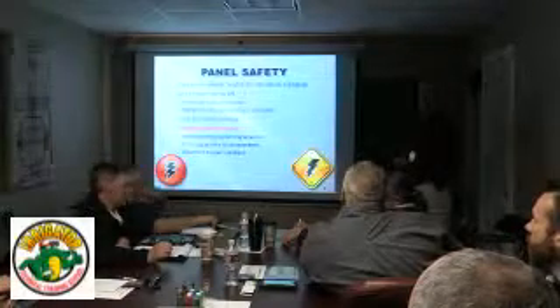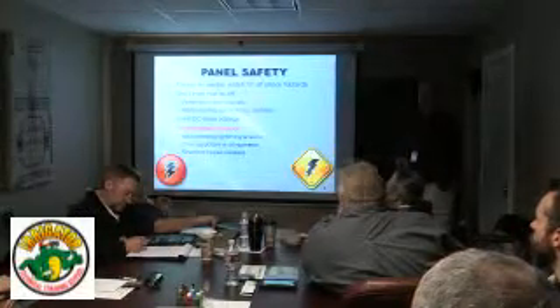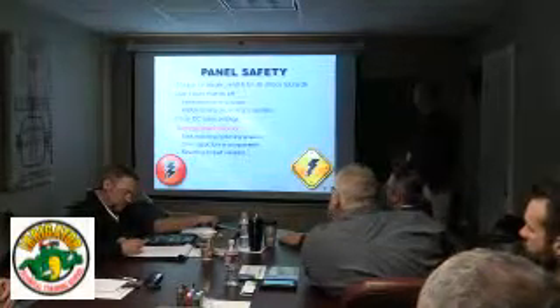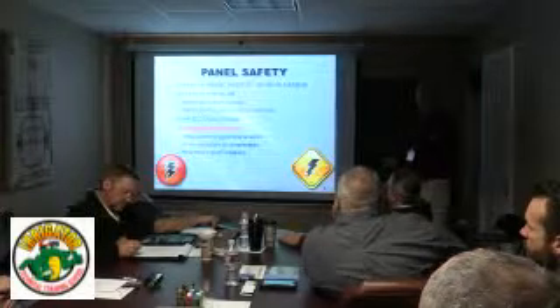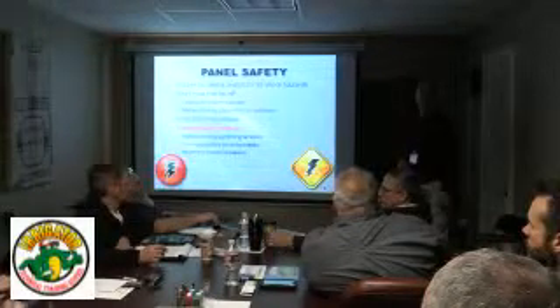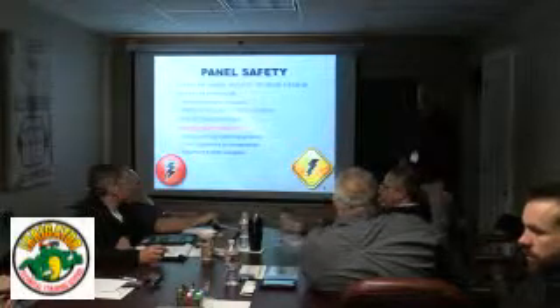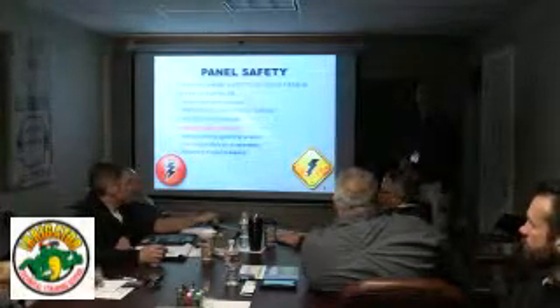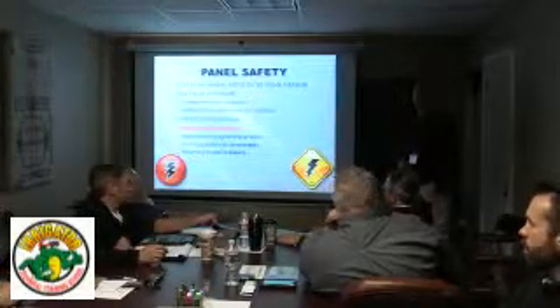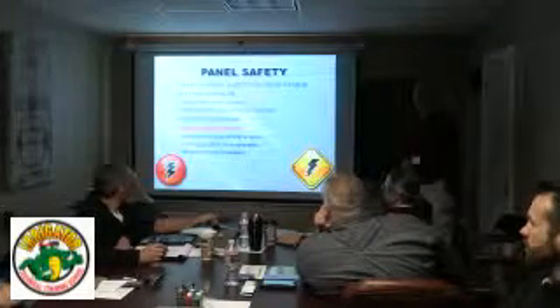Turning power back on, I always like to recommend that you close the door before you turn the power back on. If you've had to open the door to reset a breaker or for any reason, close the door before you turn it back on. I have seen a lightning arrestor explode once in my years. You might have, I've heard of overloads, breakers being damaged when it's turned back on. They tripped for a reason, you reset it, power it back up. It tries to trip again, but it might be damaged or contactor welded or something. So just always, close the door before you turn it back on.